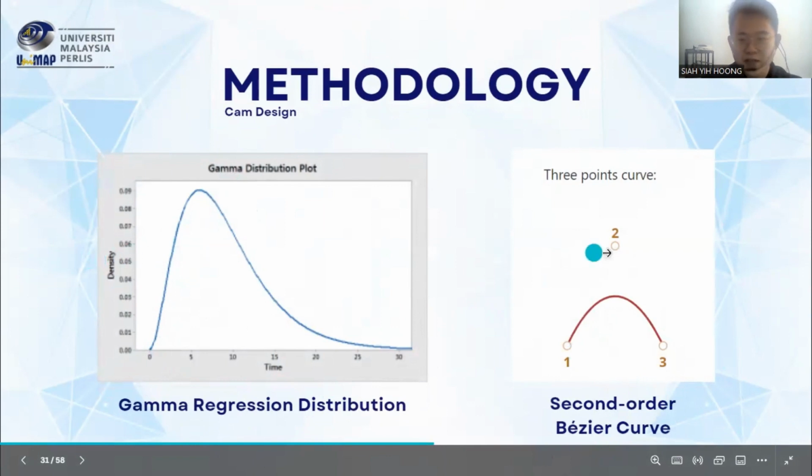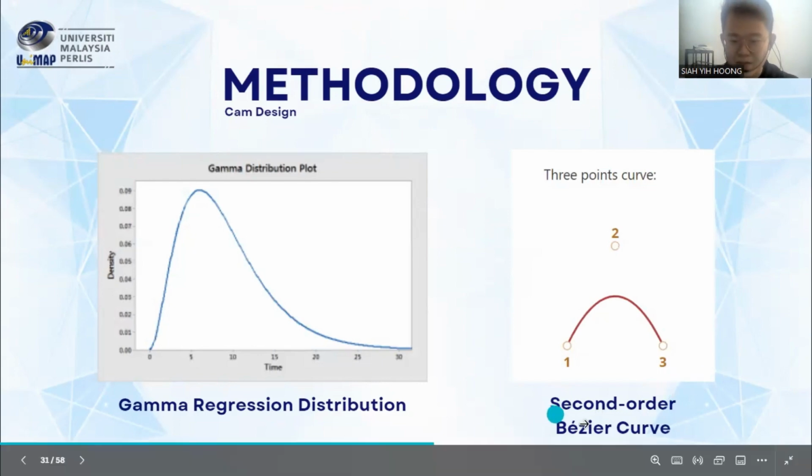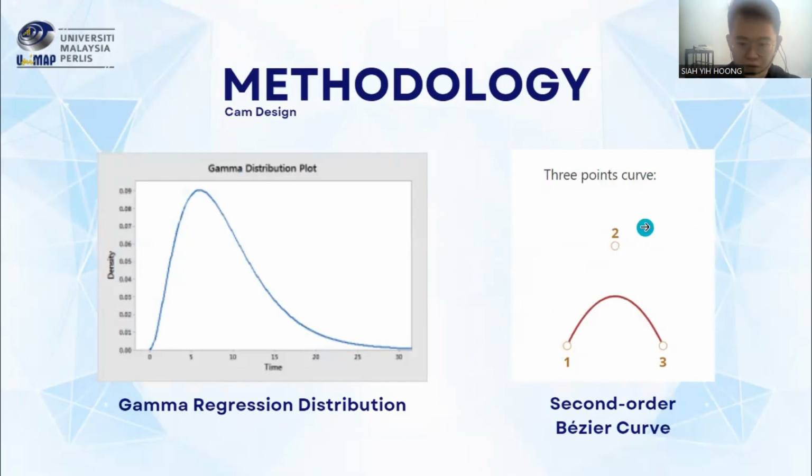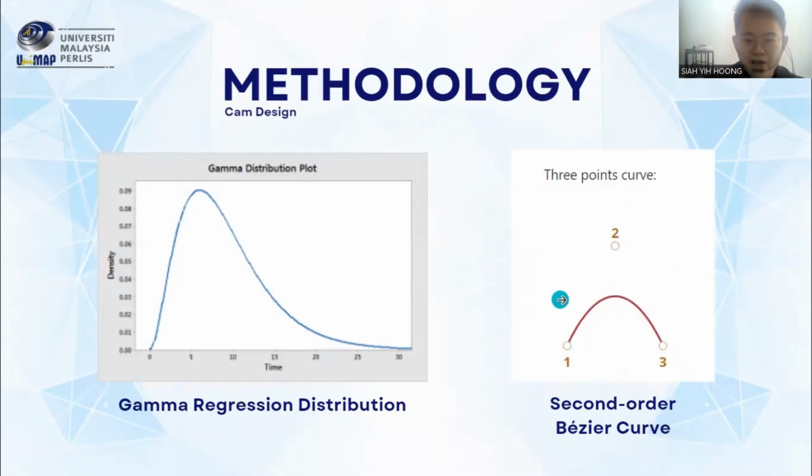Protofy.xyz also said that the ventilation waveform is actually in the form of a piecewise function, so it will be a combination of different graphs or curves. This is the second order Bezier curve. We have three points: the starting point, the ending point, and a control point. Wherever the control point is, the curvature of the line will always tend to curve towards the control point. Imagine that I have a control point here. It will curve towards here and then rotate to the ending point.